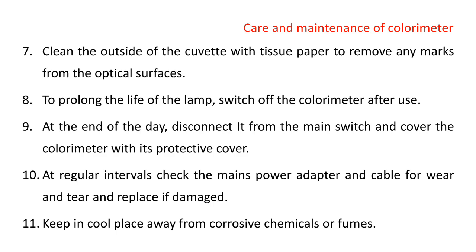To prolong the life of the lamp, switch off the colorimeter after use, usually at the end of the day. At the end of the day, disconnect it from the main switch and cover the colorimeter with the protective cover. At regular intervals, check the main power adapter and cable for wear and tear and replace if damaged. And keep it in a cool place away from corrosive chemicals or fumes.